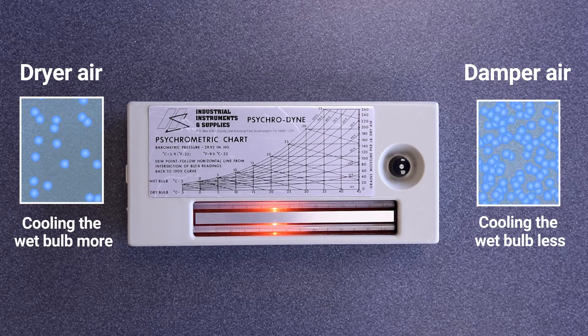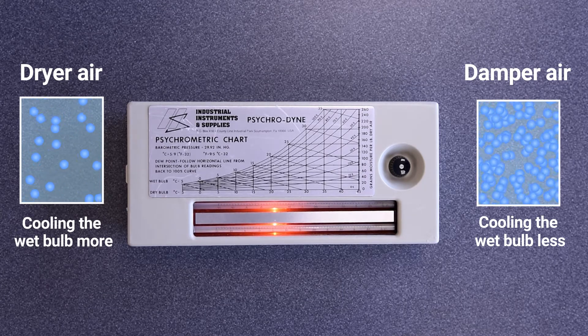Give the instrument two minutes for the wet bulb to reach equilibrium when the mercury stops dropping.